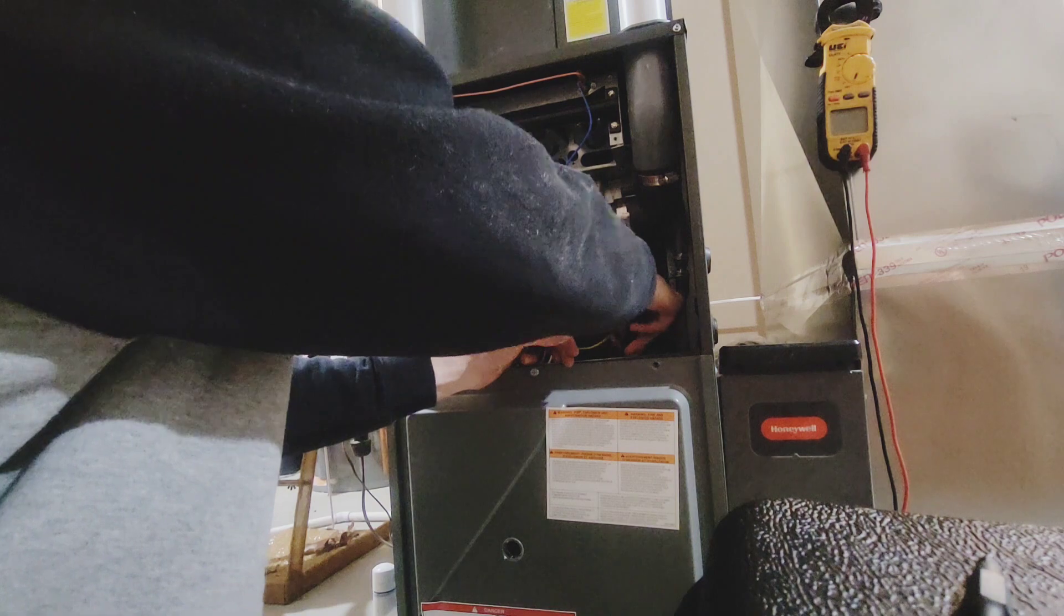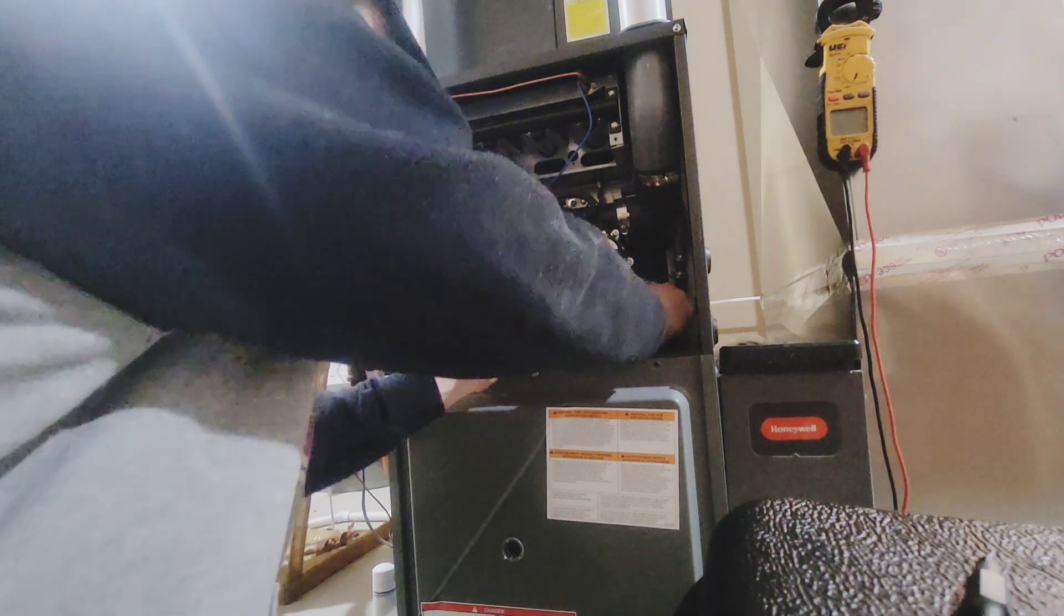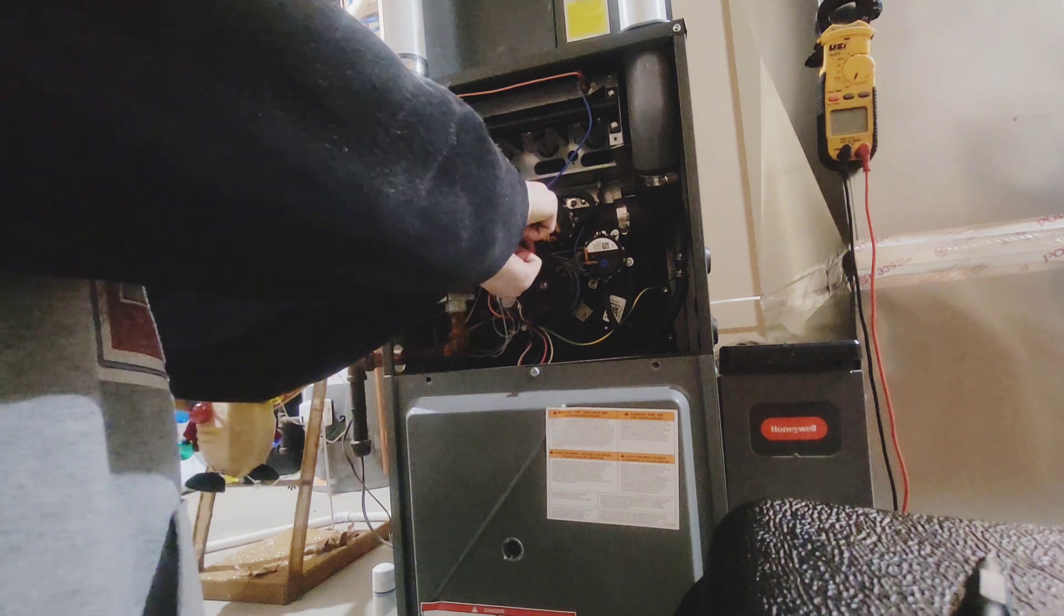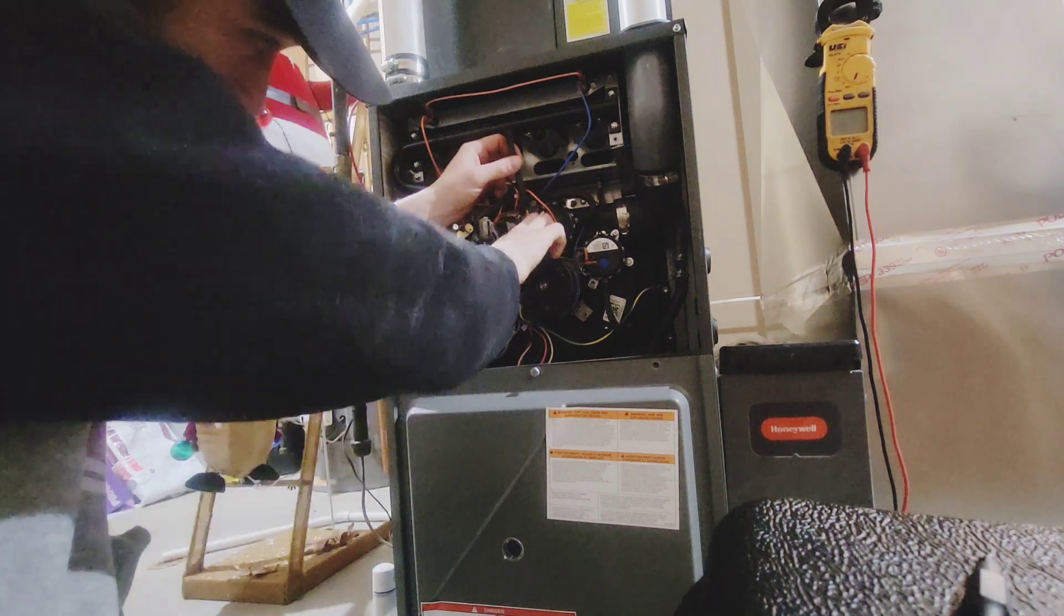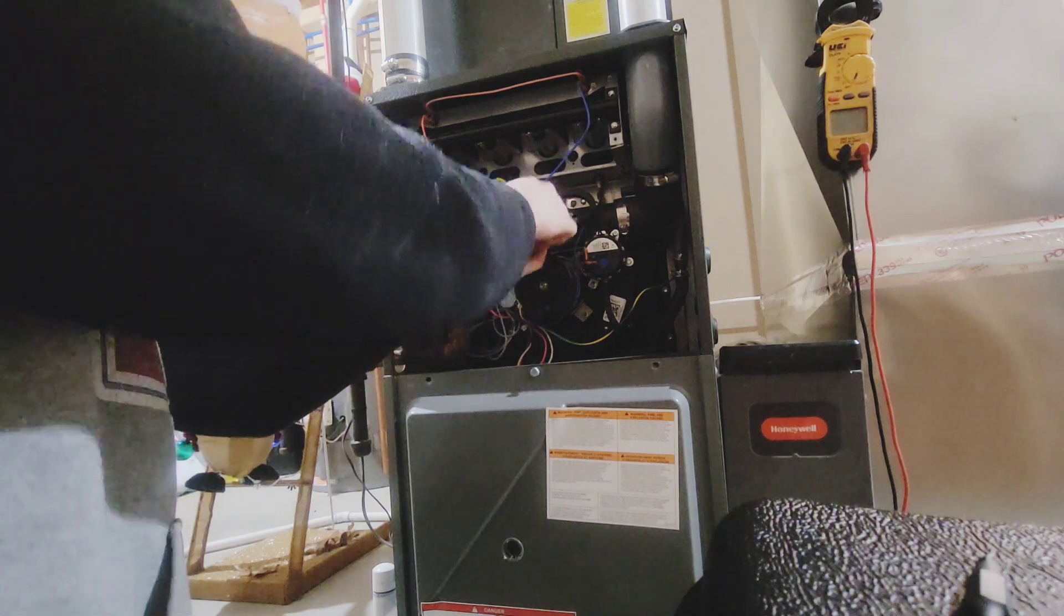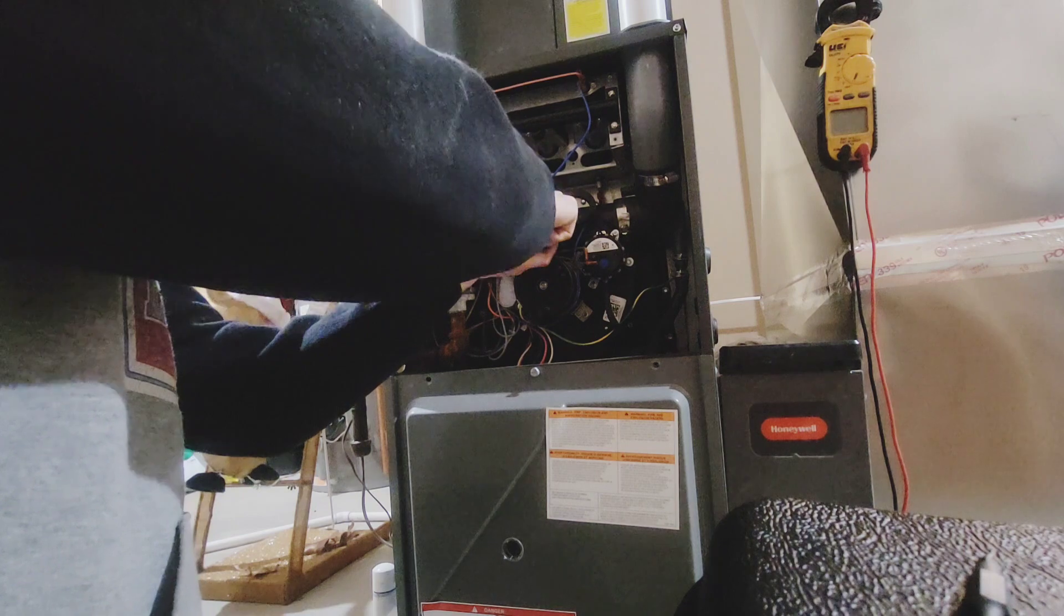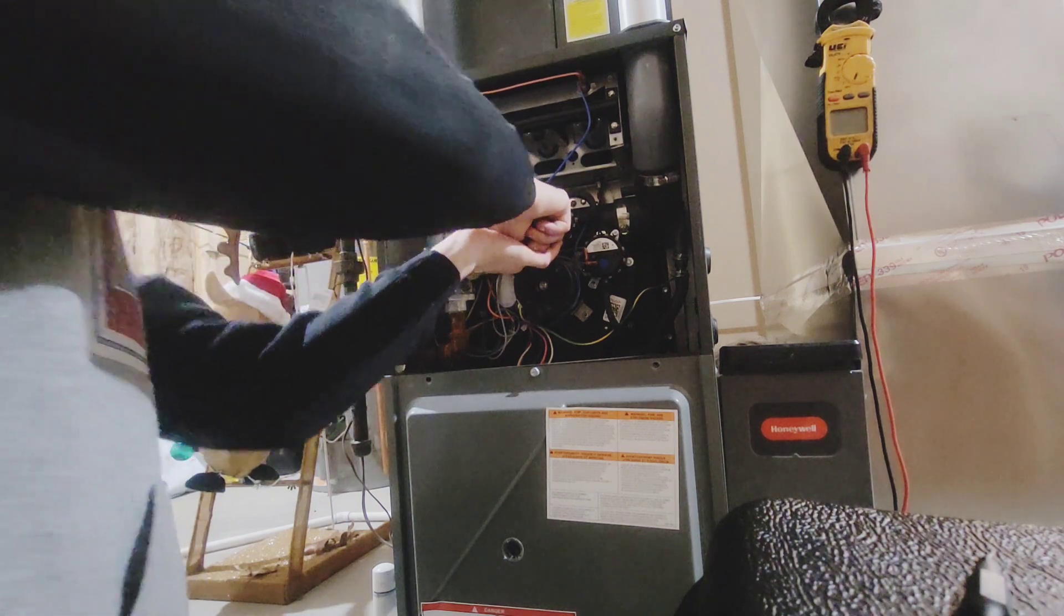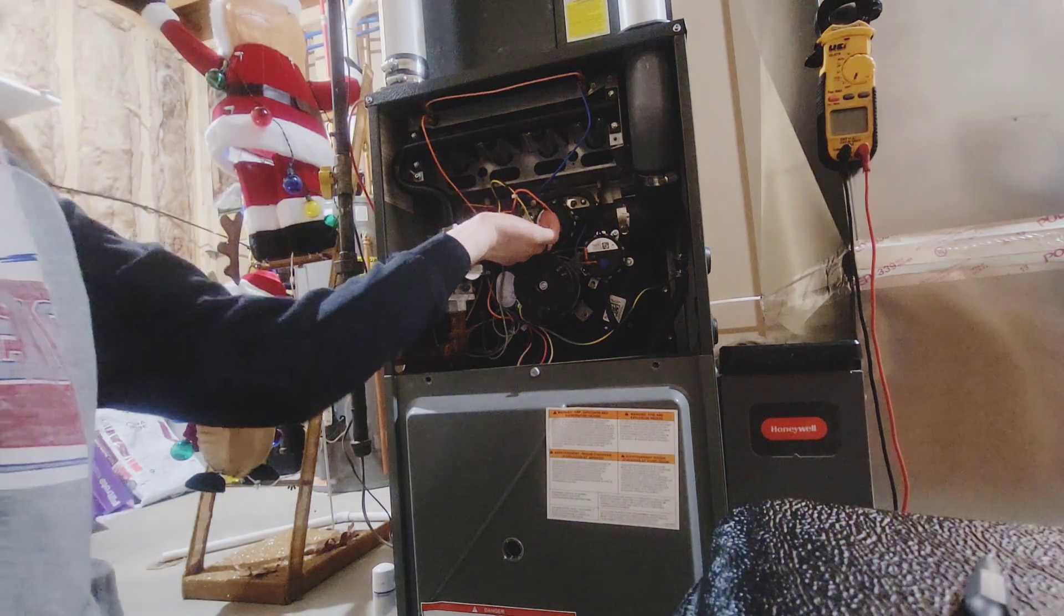We are checking pressure ports right now, drain lines, making sure everything else is clear, even though I cleaned them out last time. I want to make sure there's no other clogs in this furnace before I start it back up. Especially in the collector boxes. You want to check, make sure there's no debris in there. It's a big call that we get. Once I'm done checking with all this, we're going to push that one back in there.